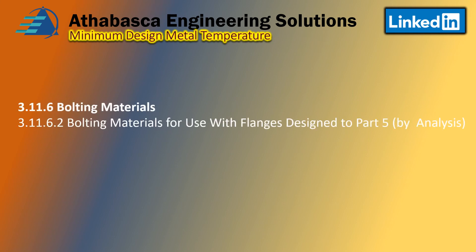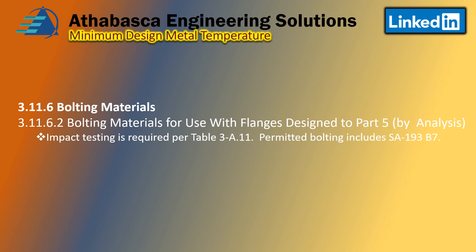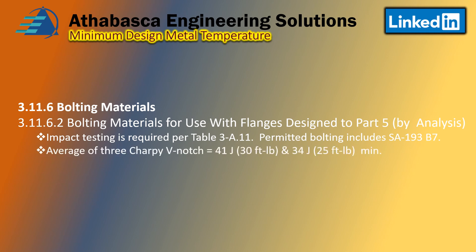For design by analysis under Part 5, impact testing is required as shown in Table 3-A.11 for bolting. Permitted bolting includes SA-193 B7, a very common bolt. When impact testing of bolting is required, there must be three Charpy tests, and the average must be at least 41 joules or 30 foot-pounds. The minimum of any of the three individual tests must be 34 joules.